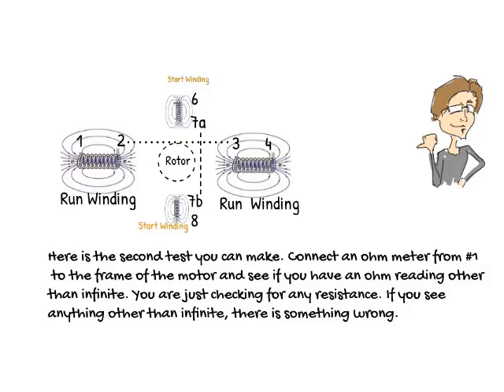Here is the second test you can make. Connect an ohmmeter from number one to the frame of the motor and see if you have an ohm reading other than infinite. You are just checking for any resistance. If you see anything other than infinite, there is something wrong in the motor.